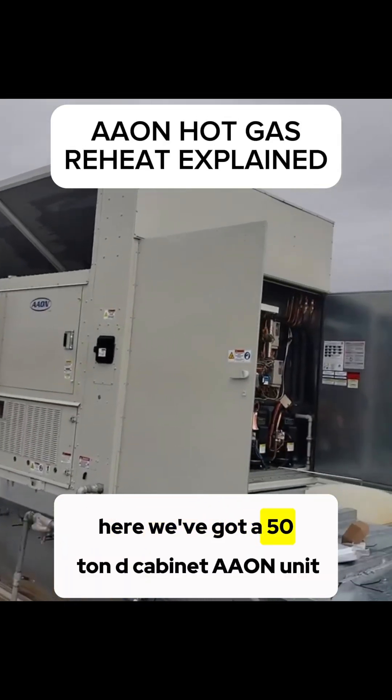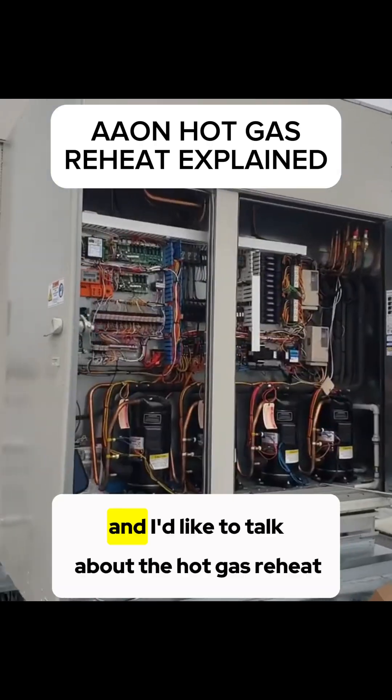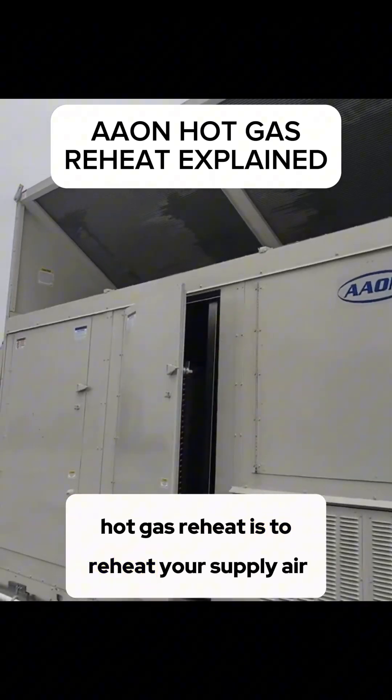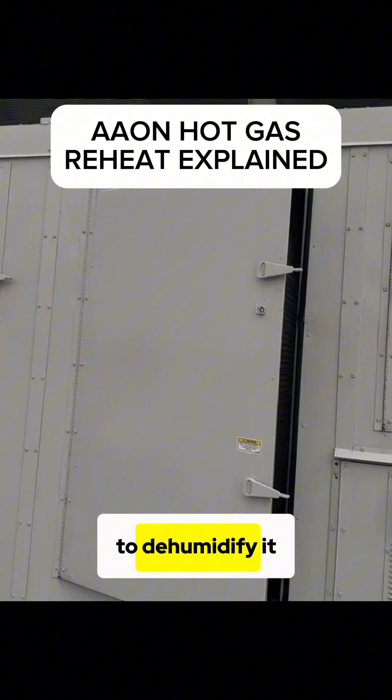Here we've got a 50-ton D cabinet AAON unit, and I'd like to talk about the hot gas reheat. Hot gas reheat is to reheat your supply air after you've cooled it off to dehumidify it.